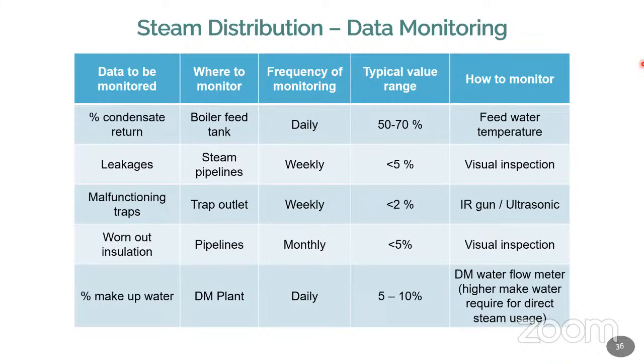Again, it depends on the process, on how many equipment are using the steam, and also whether it's a direct process or an indirect process. That will matter. But mostly the condensate water recovery is going to be very high. That's why it is represented here as 50 to 70%. So your makeup water is going to be only 30 to 50%.